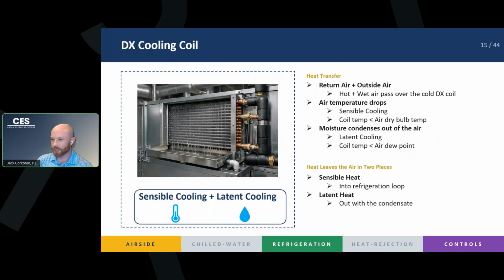And continuing down the line in our rooftop unit, right, we're going to hit our cooling coil next, right? So this is our DX, or direct expansion cooling coil. That is a little hint back at our refrigeration cycle, right? This is where the two loops meet. We're going to have our refrigeration loop, our cold refrigerant is going to be in the coil, and our hot air is going to be passing over it.